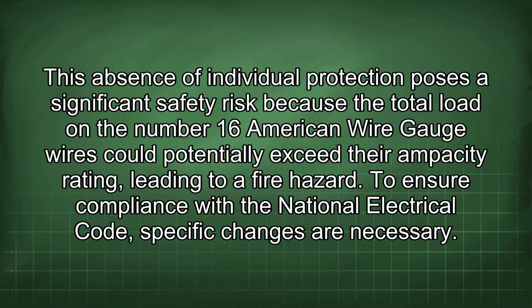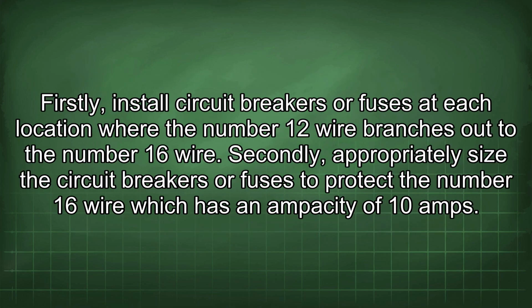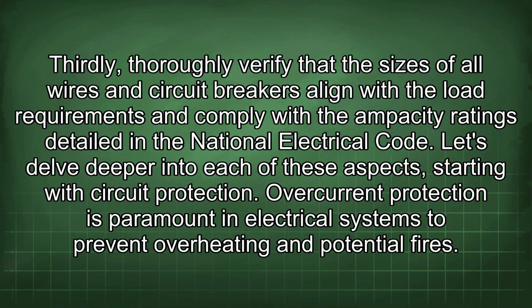To ensure compliance with the National Electrical Code, specific changes are necessary. Firstly, install circuit breakers or fuses at each location where the number 12 wire branches out to the number 16 wire. Secondly, appropriately size the circuit breakers or fuses to protect the number 16 wire, which has an ampacity of 10 amps. Thirdly, thoroughly verify that the sizes of all wires and circuit breakers align with the load requirements and comply with the ampacity ratings detailed in the National Electrical Code. Let's delve deeper into each of these aspects, starting with circuit protection.